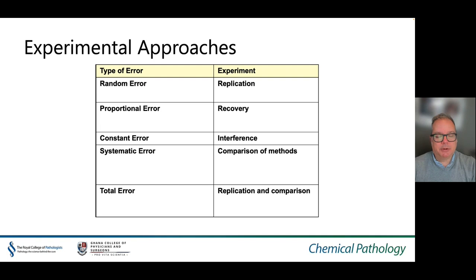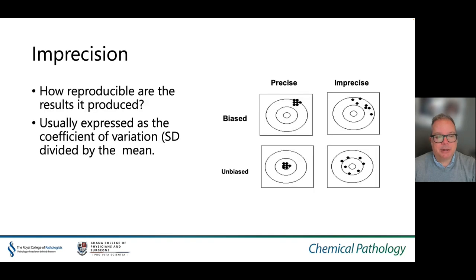In general, when performing experiments, the type of error to be determined can be broadly mapped to specific experiments — for example, random error can be determined by replication, proportional error by recovery, and so on. The results of those experiments are then compared to your specification standard. Imprecision describes how reproducible the results are and is usually expressed as the coefficient of variation (CV), which is standard deviation divided by the mean. Standard illustrations of precise and imprecise, biased and unbiased assays are detailed on the associated slide.